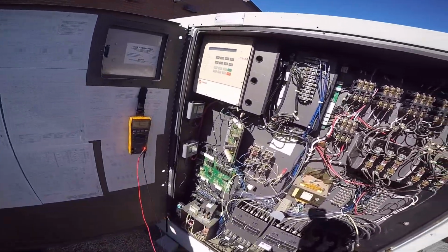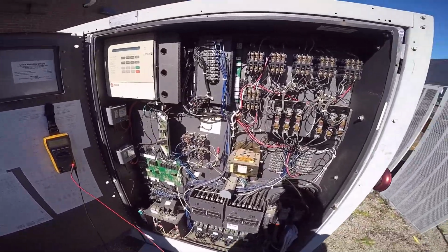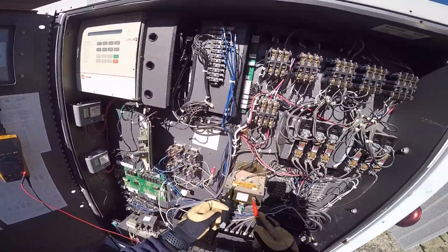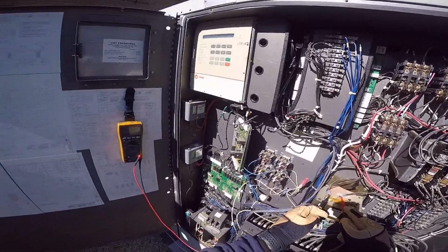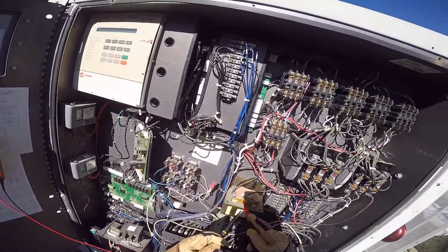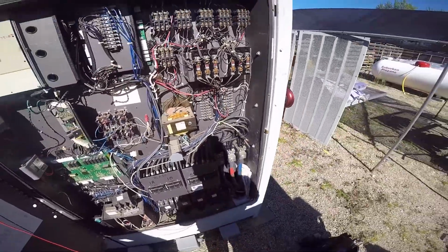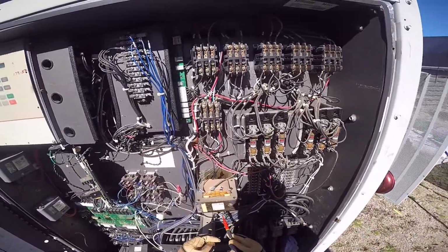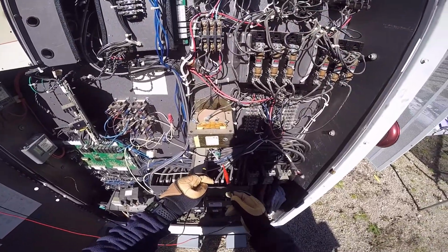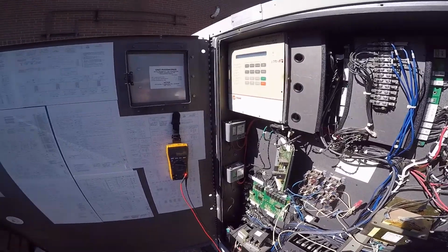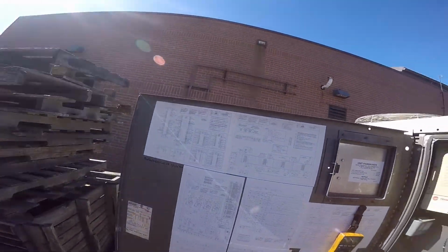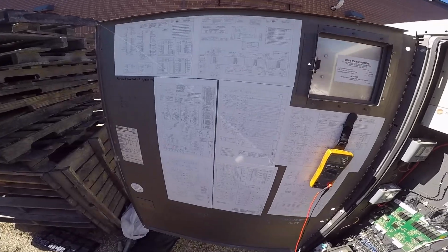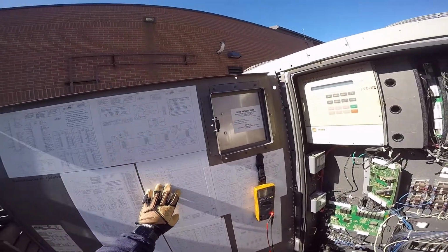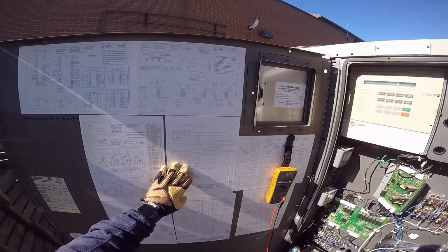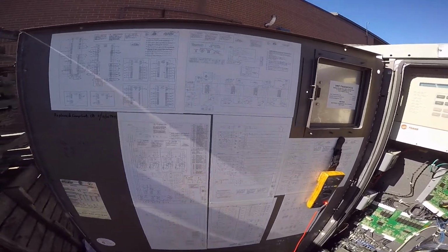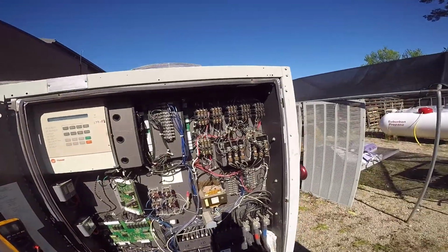So know how your meter works, so you can use your meter properly. Now what I'm going to do is come over here. I'm going to check my big transformer. I'm looking for line side power, which is 210 volts, and I got it. Now I'm going to come down to the bottom and check my outgoing power, and I believe this transformer is stepping down to 120, and it is 125. And if we need to know that and we're not sure, we have our ladder diagram over here, and we could figure that out pretty quickly.